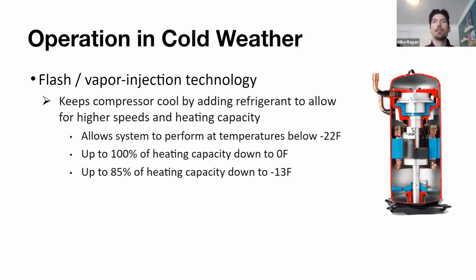And how this occurs is that with previous generations of equipment that didn't have this technology, when temperatures got so cold outside, the compressor needed to speed up to 100% speed, and it would just be running and running and running to the point it would start to overheat because it was running so fast for so long. And with that, a safety switch triggered in the system, cut it off, and made sure that your compressor didn't overheat, and the system needed to have downtime. Now, that was eliminated with the invention of flash or vapor injection technology. It has a separate refrigerant circuit whose entire purpose is to cool that compressor when it overheats in those cold climate situations.